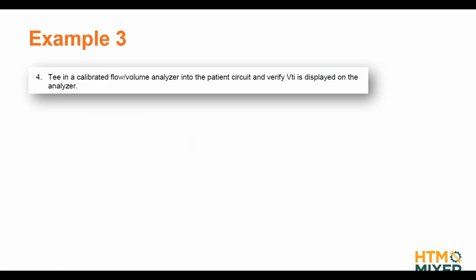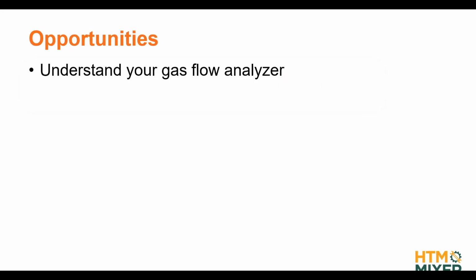Third example, this is a really nice one. Here, the manufacturer just says, tee in a calibrated flow analyzer that can measure tidal volume, and everything else, they leave it up to you to figure it out yourself. Right, so that's not very supportive, of course. Of course, we can't expect all the manufacturers to show pictures for each and every flow analyzer which is out there in the field, right? And that's why it is very important that you understand your gas flow analyzer, right?